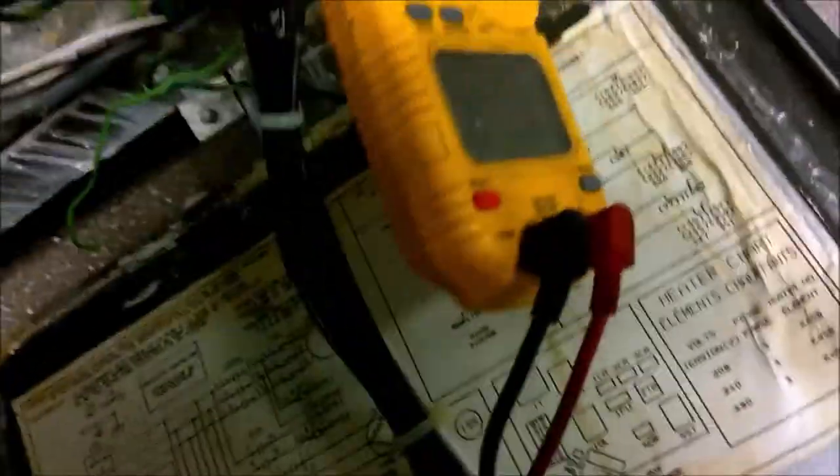I'm just going to take an amp draw now that the plunger is no longer pulled in to make sure there's no bleed through on this contactor. We want zero amps across all three legs, which we do have.